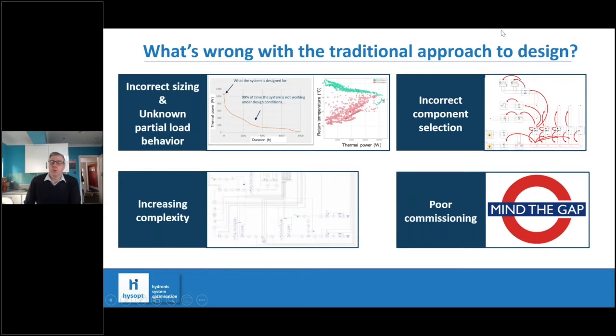And if we look at where we are now and look back in the past, the problems we've had with heat network performance have all started around the way those systems are designed and developed. And I think these issues have been discussed quite a lot in previous Minibems webinars as well. So for us, there's a number of key things. Firstly, incorrect sizing and unknown partial load behavior of the system. Traditional approaches tend to be based around peak, static load, and rules of thumb for sizing, and it just results in systems that are oversized and perform poorly under partial load conditions.